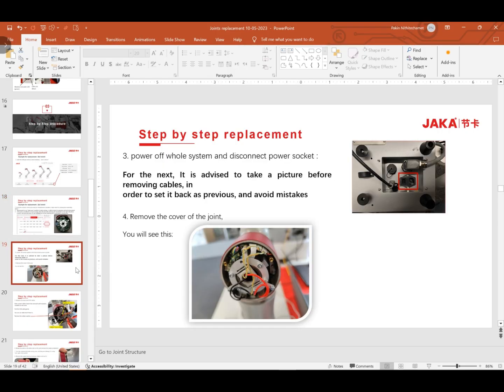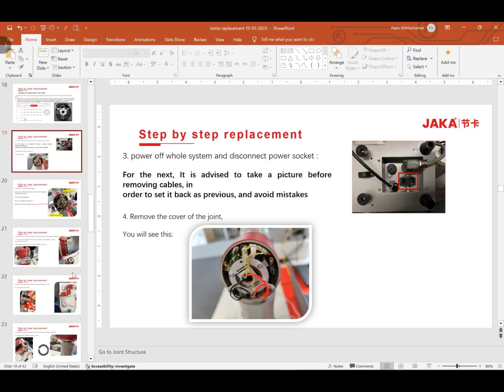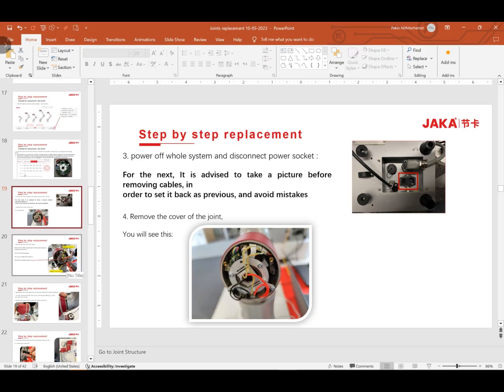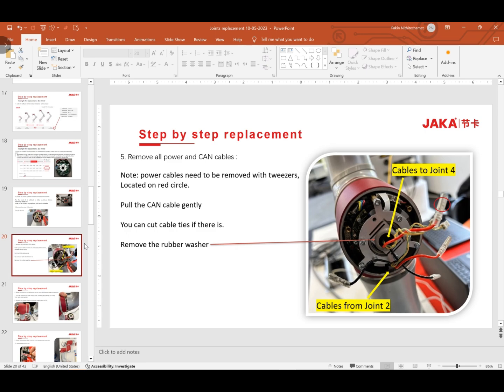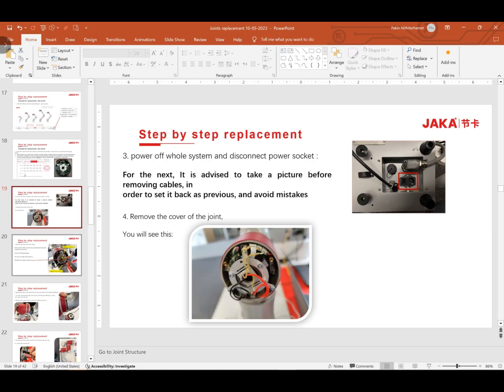After moving to that position, we power off the controller, and then we remove the joint. After removing the cover of the joint, you will see the power cable, then you remove it. But it's very important that after you remove the cover of the joint, you need to take a picture first, so when you assemble it back, you will know how to wire the cable.